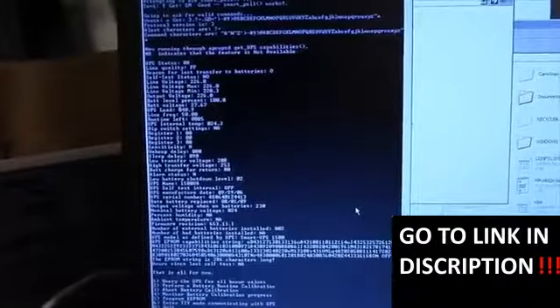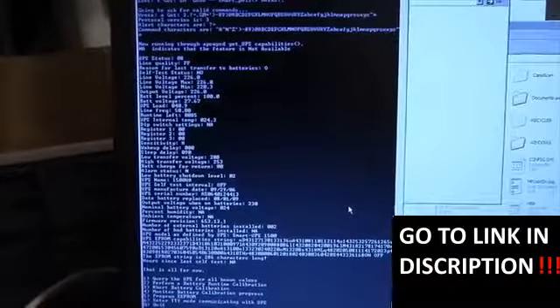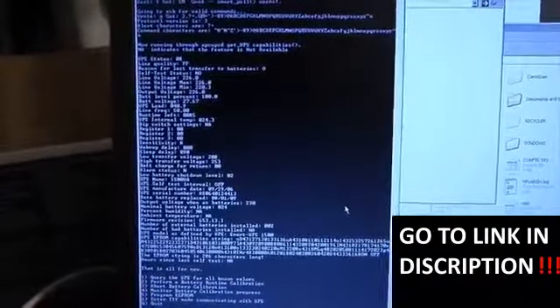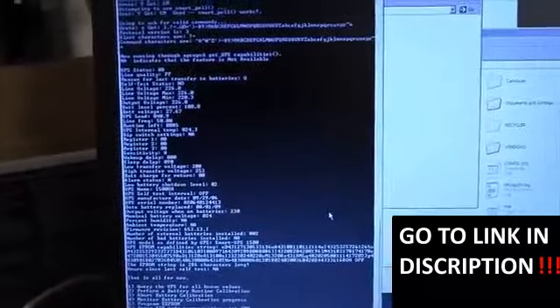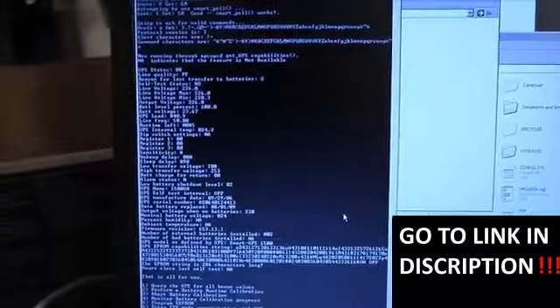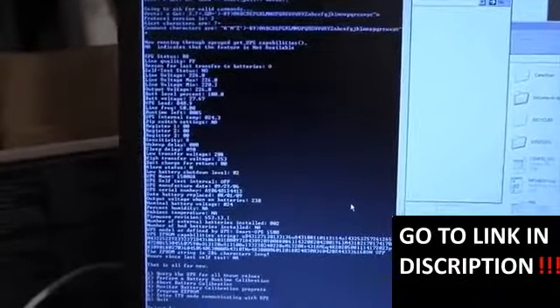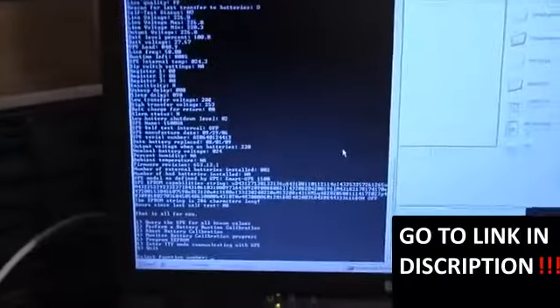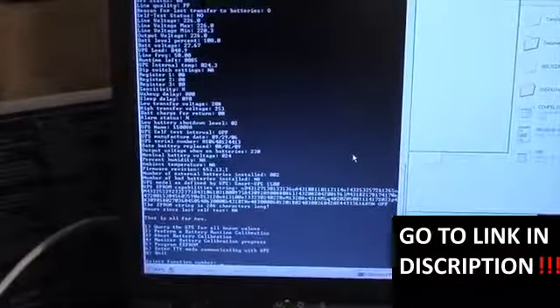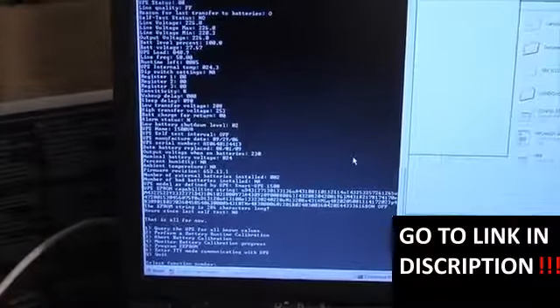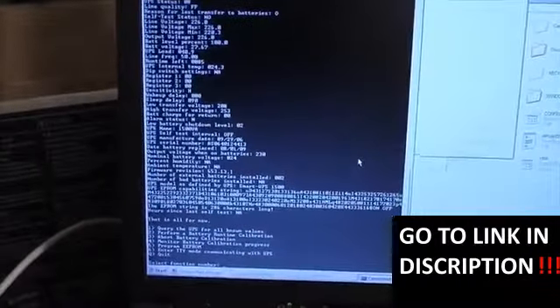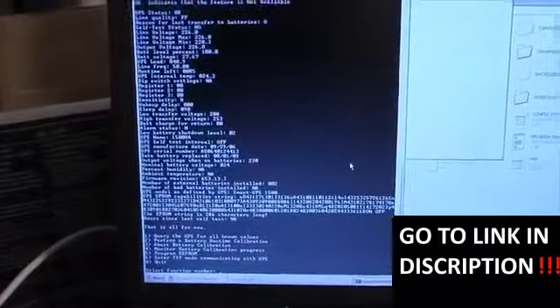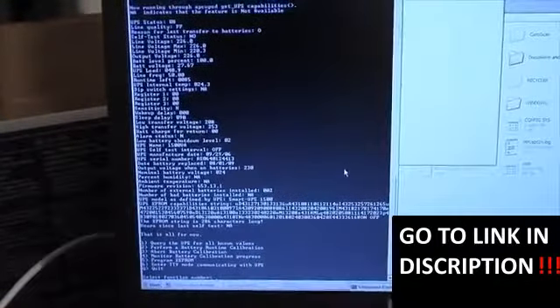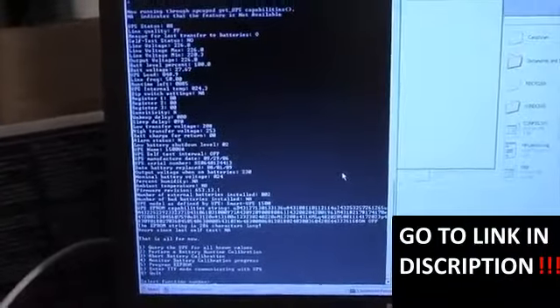Well, that's kind of reasonable. I think I must have reset it. I thought it calibrated itself down to almost no runtime at all. Anyway, I'm gonna go into the configuration mode and raise the battery constant anyway, to make it think it's gonna run for ages, and then run a battery calibration to get it down to a realistic level.